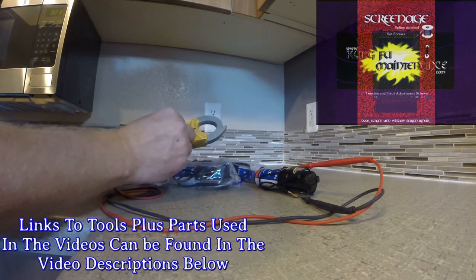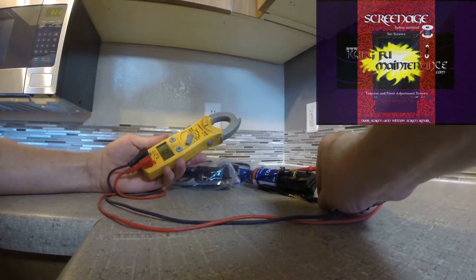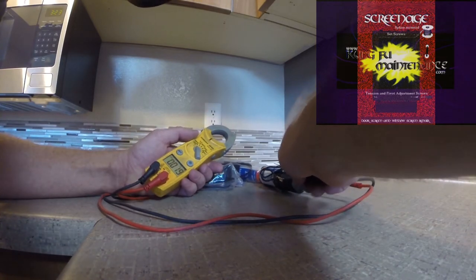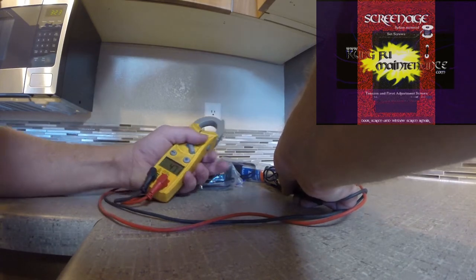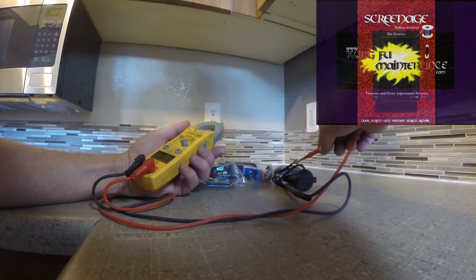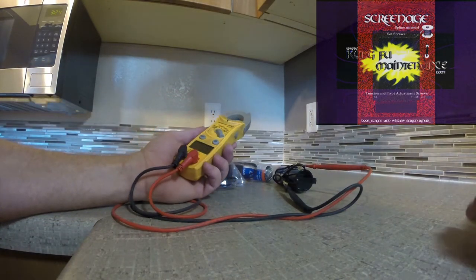I'll flip this over and test the microfarads. What I found was about 47.4 earlier. We need a good test here. Getting readings of 46.9, 47.1, and about 47.4 — so we're showing around 47. Now that's on this one.